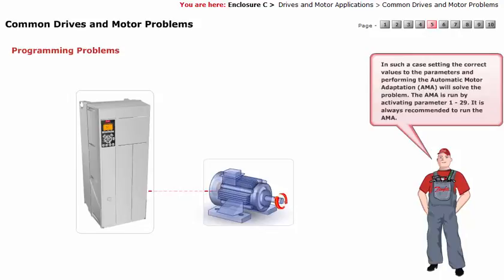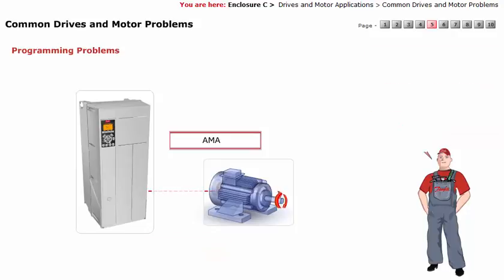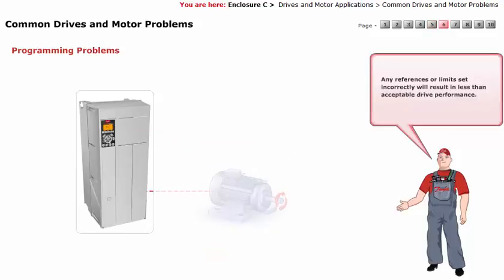In such a case, setting the correct values to the parameters and performing the Automatic Motor Adaptation (AMA) will solve the problem. The AMA is run by activating parameter 1-29. It is always recommended to run the AMA. Any references or limits set incorrectly will result in less than acceptable drive performance.